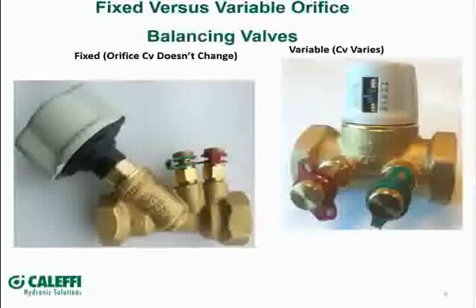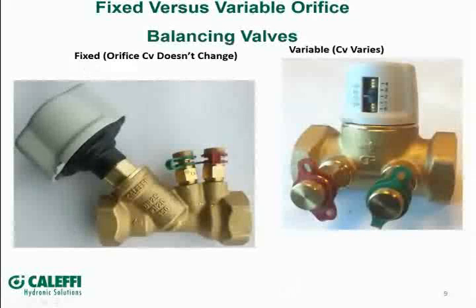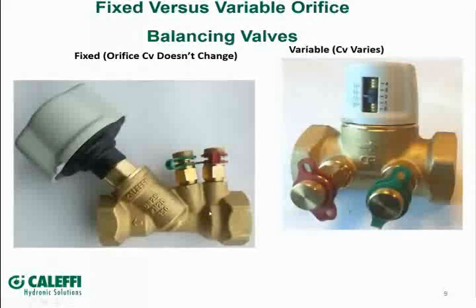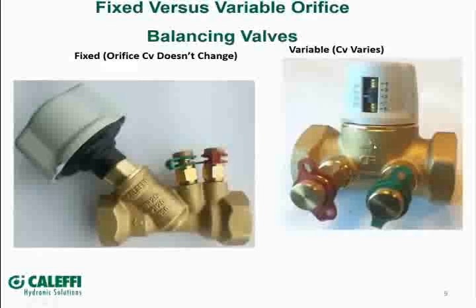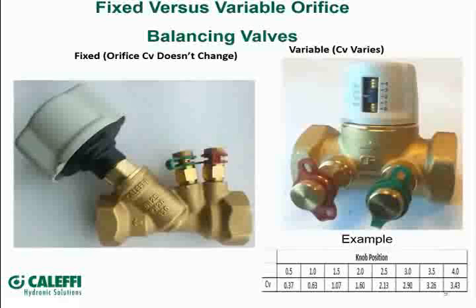Here's an example of a couple of balancing valves. Both are used to balance flow through a hydraulic or fluid system. You'll notice these two valves look a little different. The valve on the left is a fixed orifice — the CV doesn't change on this valve. The valve on the right has an adjustment mechanism, and you can actually vary the CV of this valve. Let me show you what that looks like on the data sheet that would come with this valve.